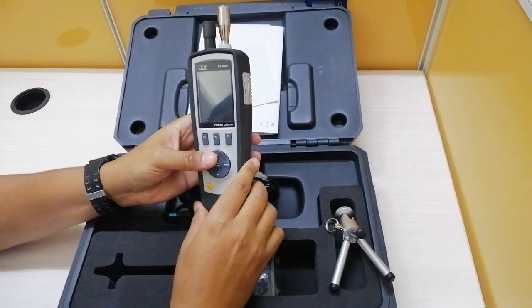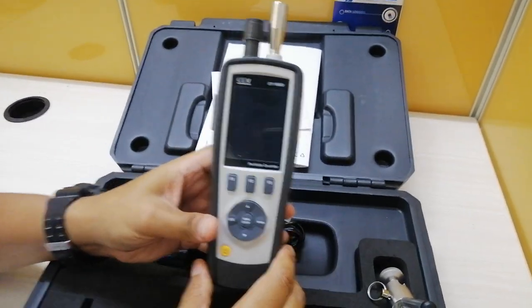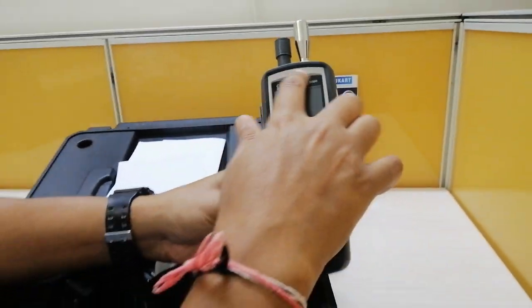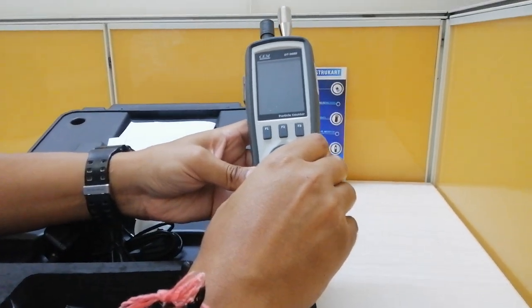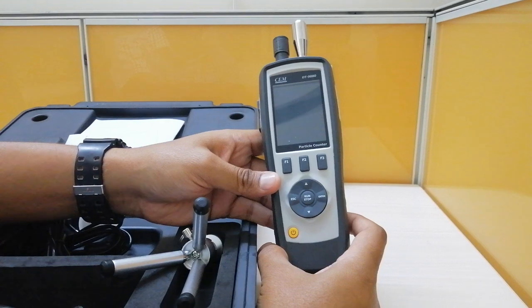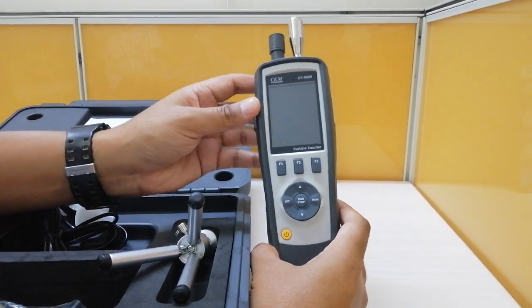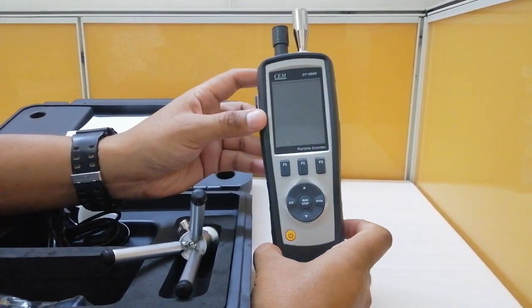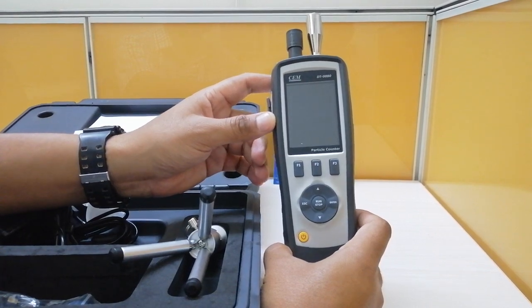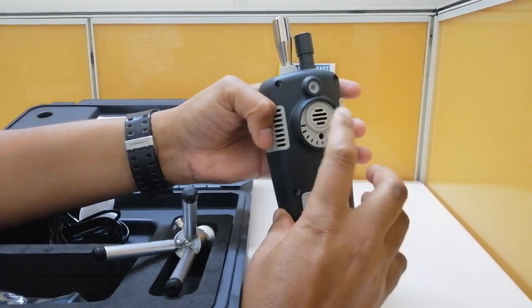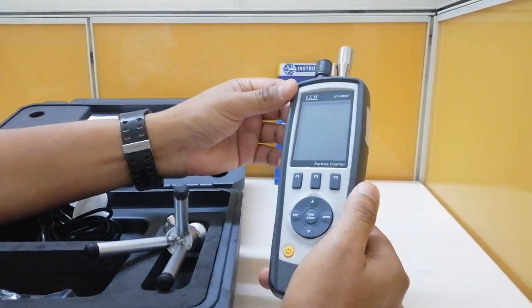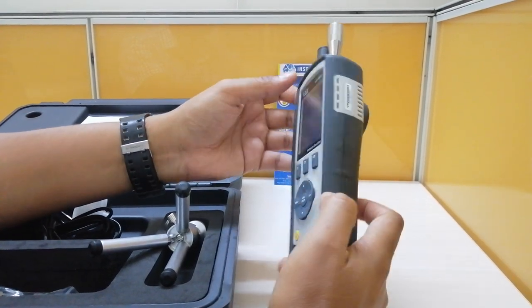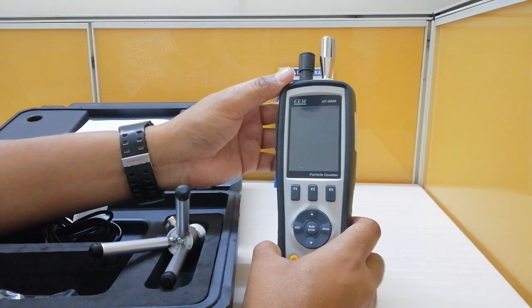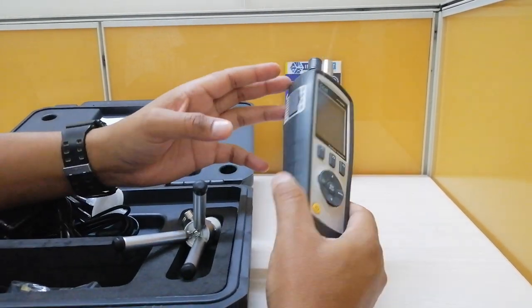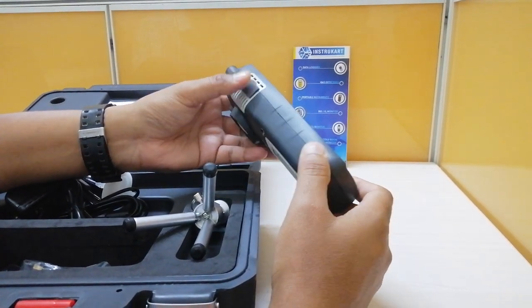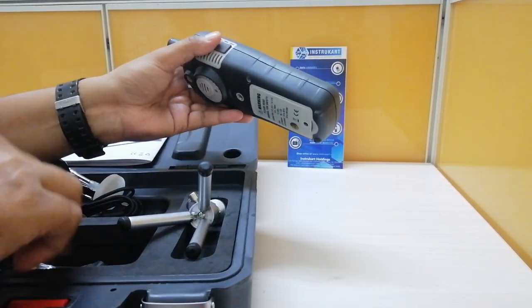Now coming to this particle counter, the basic features are a 2.8 inch TFT LCD display, and the best part is that it has 6 channels, which we get in expensive models of particle counters. We have got it in this model also. It supports air, dew point, wet bulb temperature and humidity measurement, and it supports image capture from this camera, and also video capture in 3GP. It has a setup control for date and time and other controls, and a USB interface is also available with the data logging feature. We can also put in the microSD card as just shown a while back.